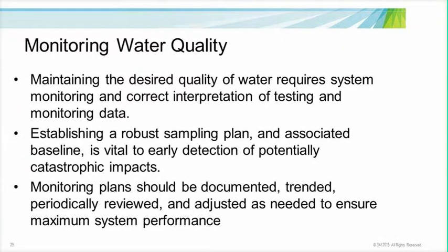Once a quality water system is properly installed and validated to meet the required grade of water, implementation of a process control system and best practice are crucial in maintaining the water system and associated quality. Maintaining the desired quality of water not only requires system monitoring, but correct data interpretation and training of test data results. Establishing a robust sampling plan and developing an associated baseline for action and alert levels is vital to early detection of potentially catastrophic impacts or out-of-spec conditions. These monitoring plans should be documented, trended, periodically reviewed, and adjusted as needed to ensure maximum system performance.